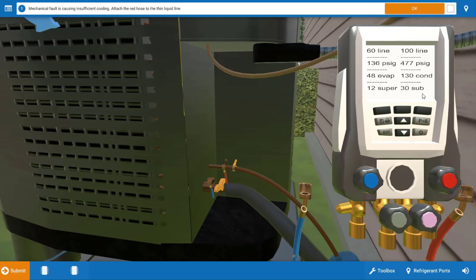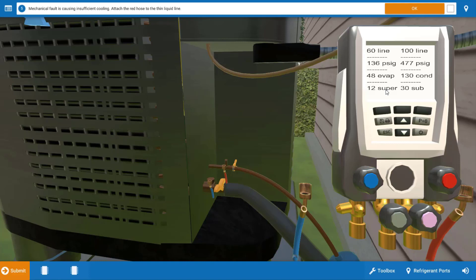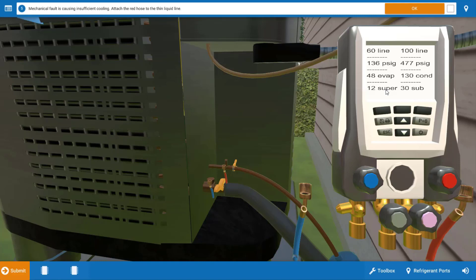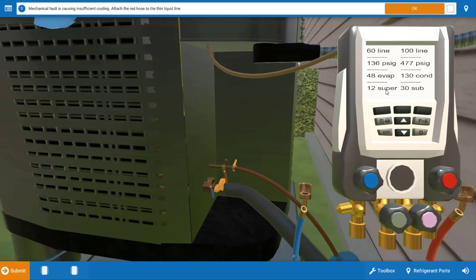First of all, our superheat is normal and that's okay. The TXV metering device is going to maintain superheat in the event of an overcharge. However, if we look at the evaporator temperature it's kind of high, just slightly high at 48 degrees. Generally an air conditioner should operate somewhere between 35 and 45 degrees. The warmer evaporator is going to result in less heat being absorbed and it's going to cause the unit to run longer to make temperature as well as draw more amperage, which means more power consumption while it's on. So this is a pretty inefficient condition.